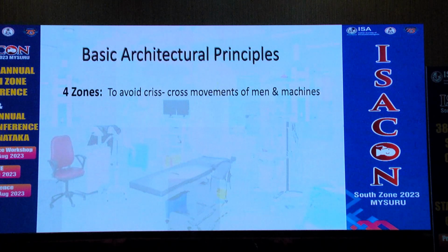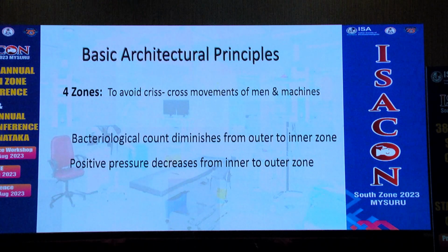The basic principle is that there should be a four-zone distribution. That is to avoid crisscross movement of man and machine. In these four zones, the bacteriological count diminishes from the outer to the inner zone, whereas the positive pressure decreases from the inner to the outer zone.